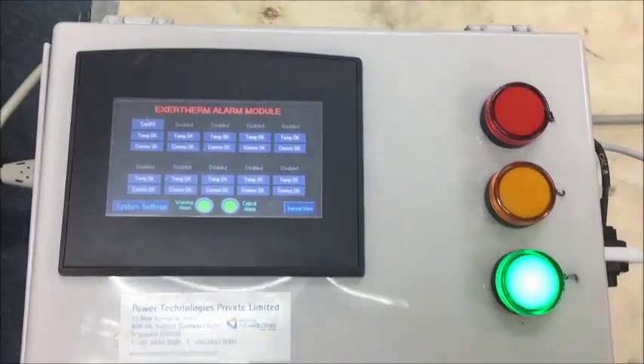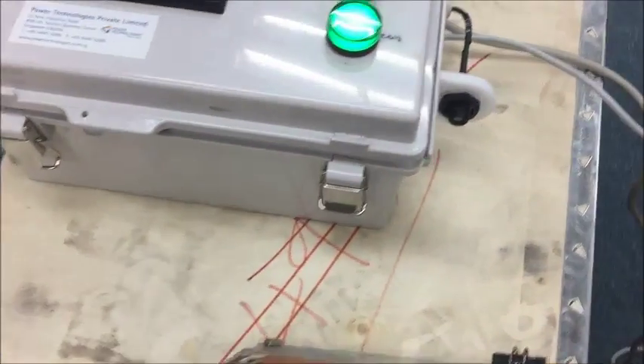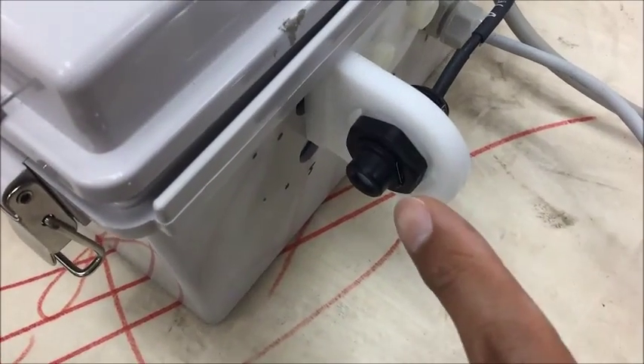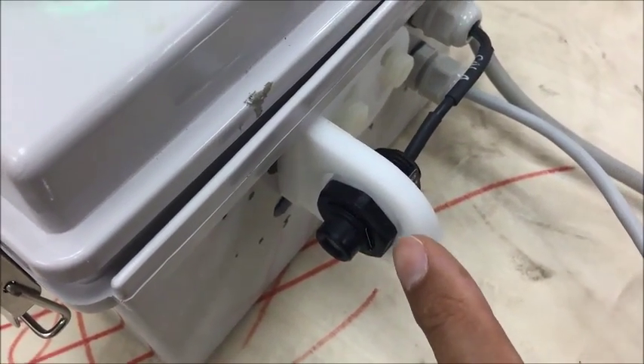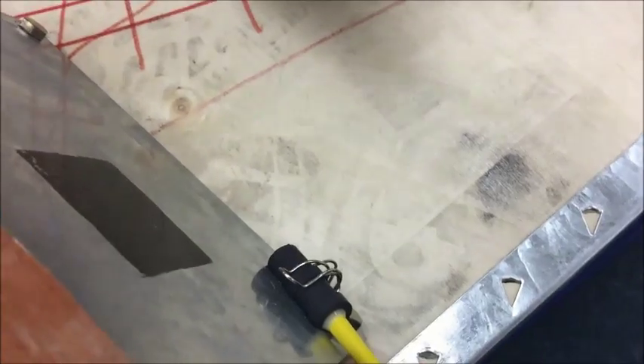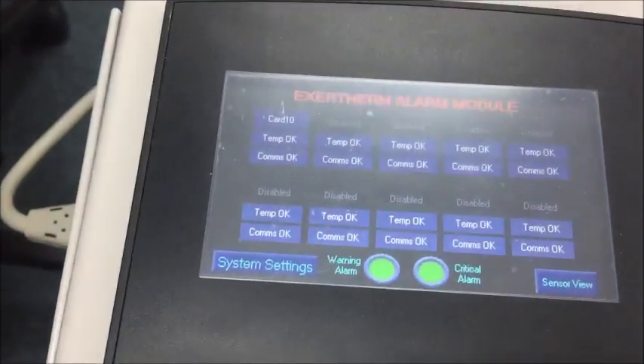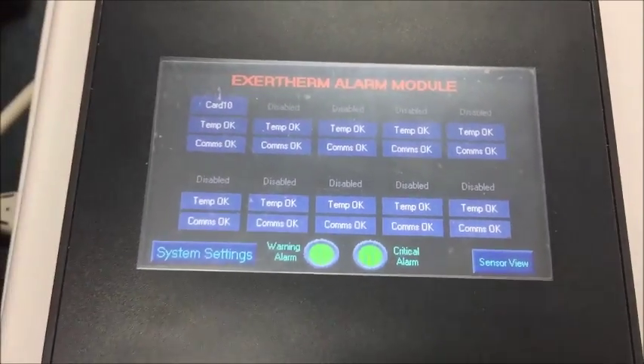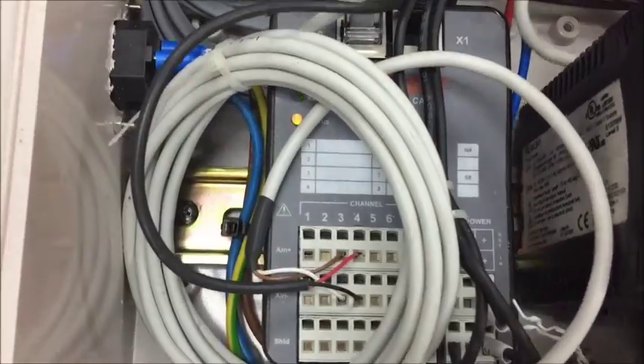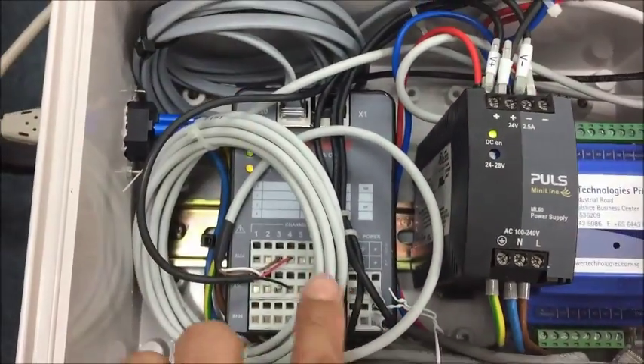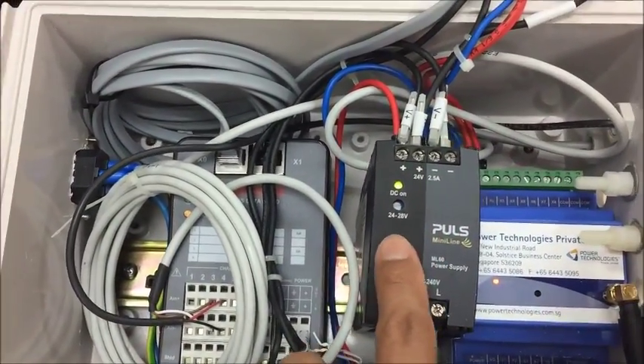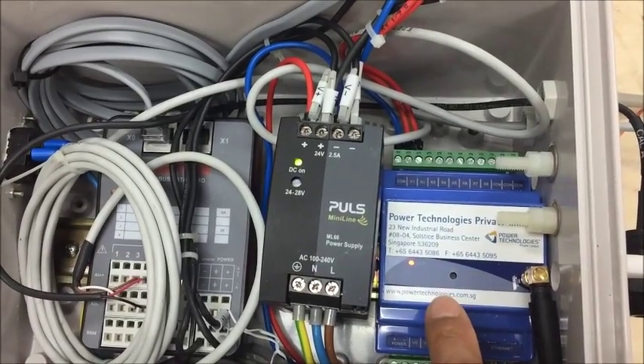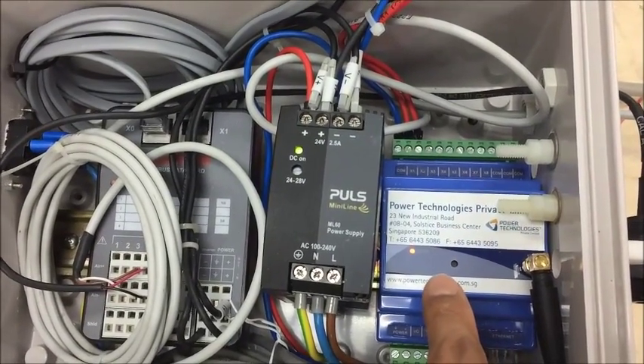Exertherm condition monitoring system. This is an infrared IR sensor. This is a cable type sensor. This is an alarm module. Localized, and we got a data card inside, and a power supply unit. We got the remote system with SMS capability.